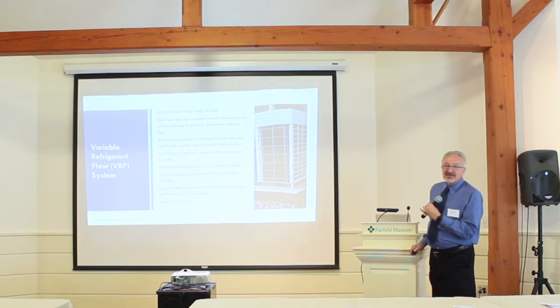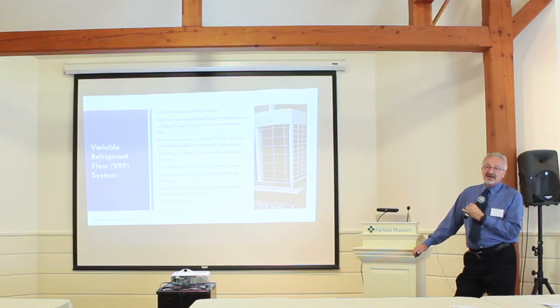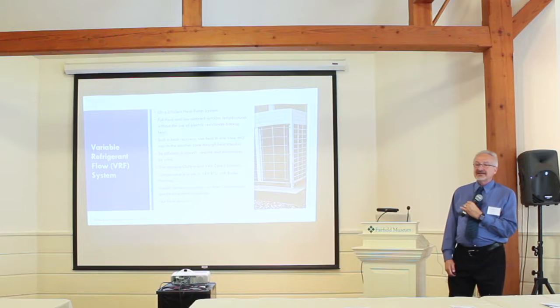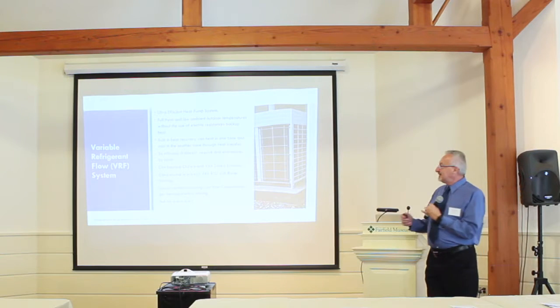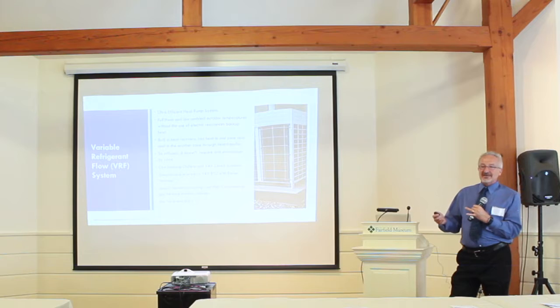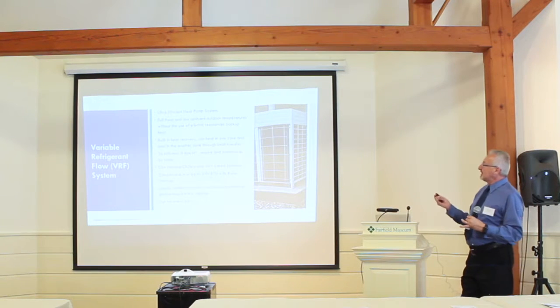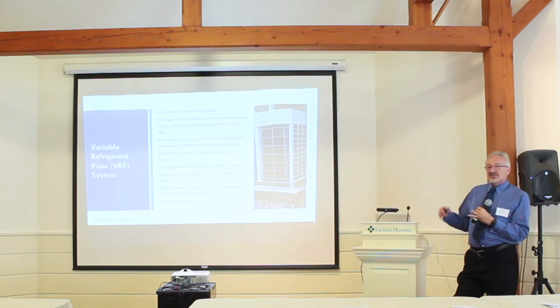The other new technology is variable refrigerant systems. There's some complexity to them, but are they efficient? Yes, they're very efficient. I just finished a model for a customer of ours who is putting in about an 8,000 square foot office building, and we compared conventional systems to high efficiency systems. Going from a baseline system to a high efficiency system on this particular building, the customer would save $2,000 a year. Going to a variable refrigerant flow system, the customer is going to save $6,000, $7,000, $8,000 a year.